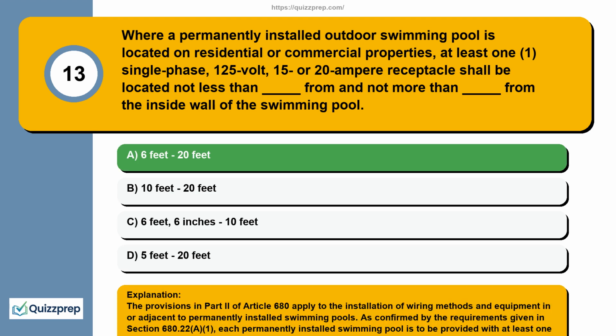The provisions in Part 2 of Article 680 apply to the installation of wiring methods and equipment in or adjacent to permanently installed swimming pools, as confirmed by the requirements given in Section 680.22 a. 1. Each permanently installed swimming pool is to be provided with at least one single-phase, 15 or 20 ampere, 125-volt, receptacle placed not closer than 6 feet from the pool and not more than 20 feet from the pool.